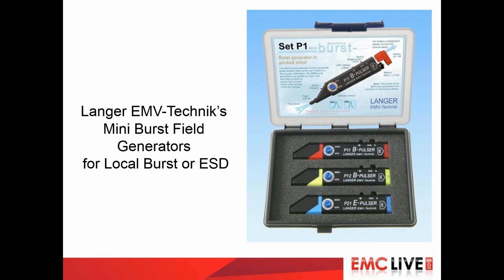Both magnetic probes are capable of 2 nanosecond to 8 nanosecond type rise times, single pulse or 5 kilohertz frequencies. So those are wonderful. Then you have an electric field probe capable of localized fields up to 100 kV per meter. Like I said, it's extremely localized. Wow. These are handheld battery-operated devices, and you can see, I don't know if my arrow shows up here, that it's designed to generate that field right there at the tip. So that's the concept, for doing board work where you can do testing in a very localized area.